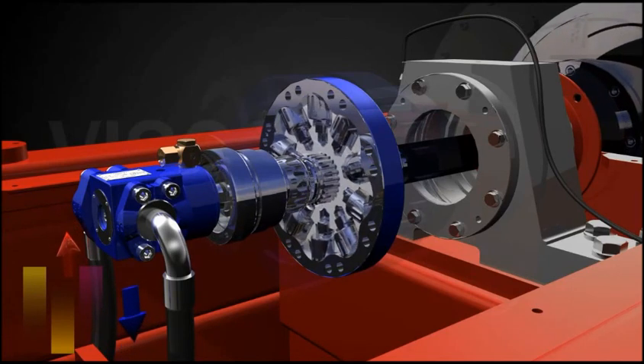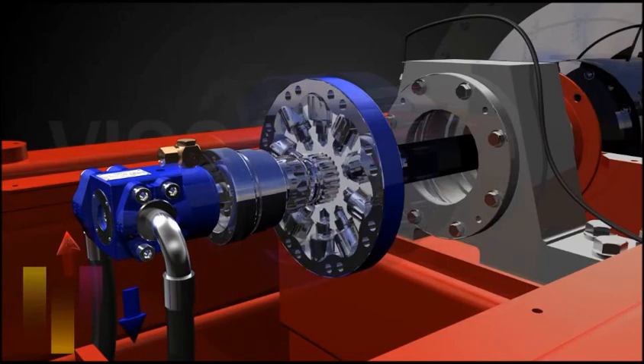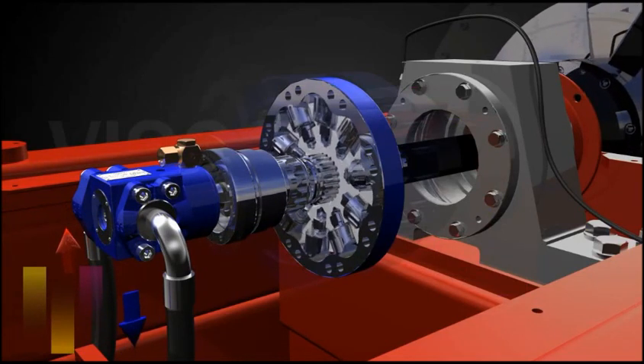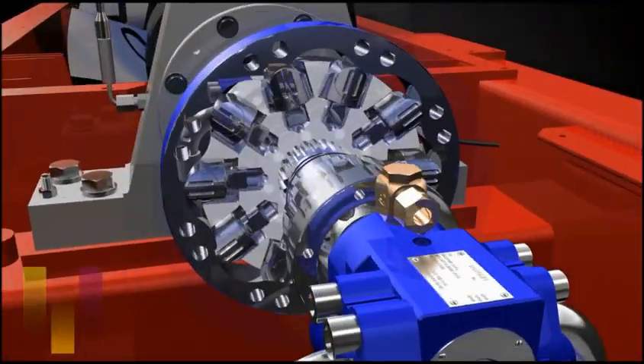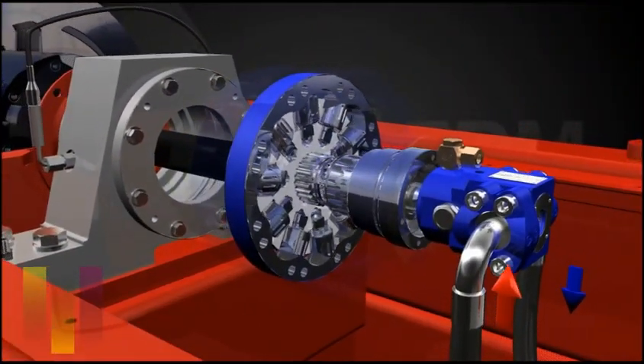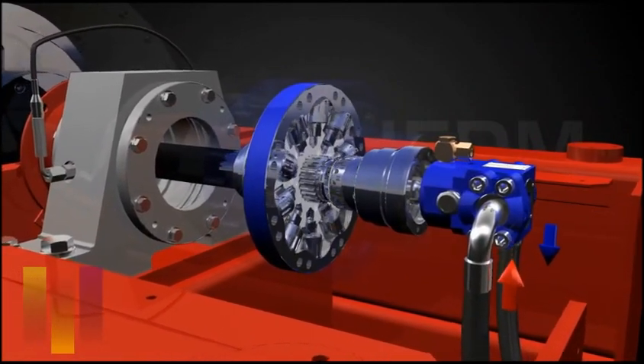The solid loading, or conveyor torque, is directly proportional to the hydraulic system pressure. This allows simple and direct speed control, which enables immediate response to any process changes. In combination with the highest torque capability, throughput capacities and cake dryness can be improved.